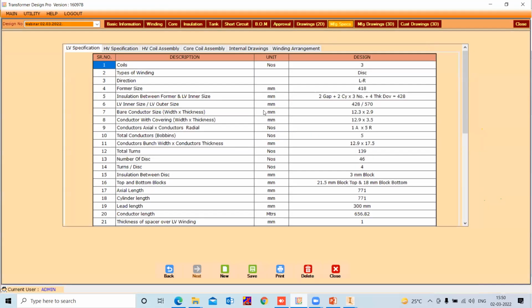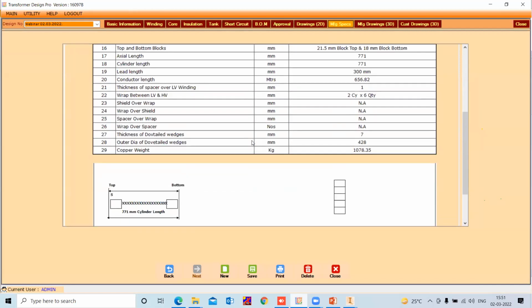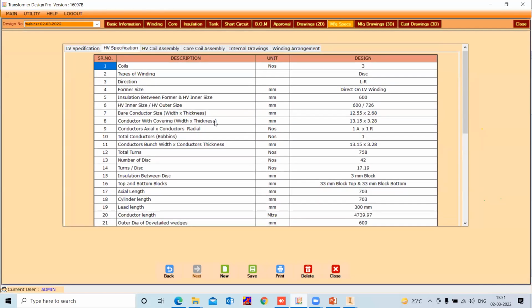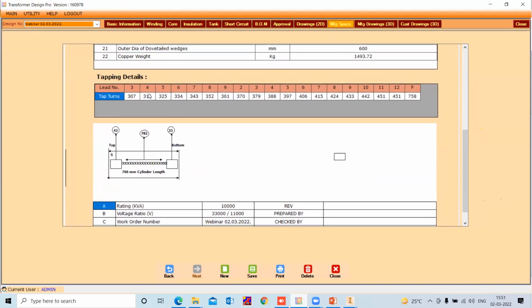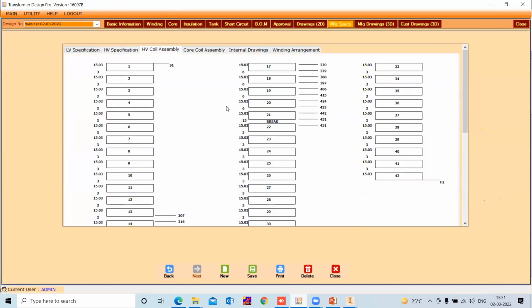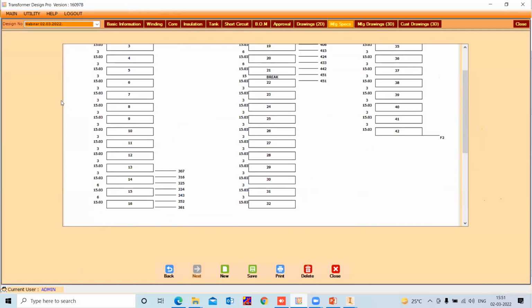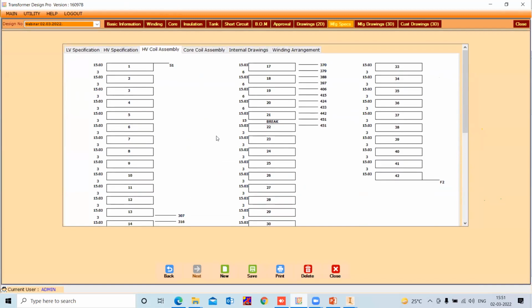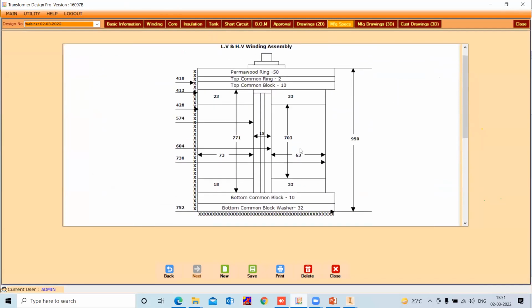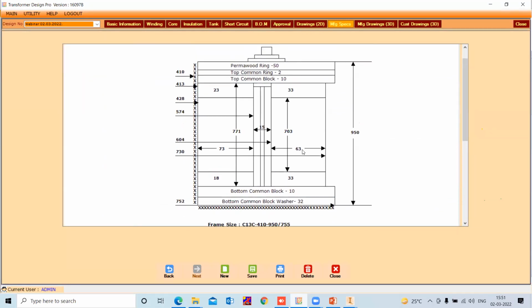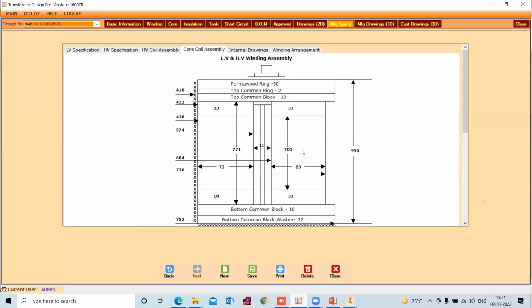Now, let's see the manufacturing specification for shop floor. Then this is the LV winding detail, HV winding detail. You can see the tappings for OLTC, the lead number and tap turns. Then the HV coil assembly. You can see the insulation arrangement in between the discs. There is a 3 mm insulation, but between the tappings, the insulation will change automatically. Now you can see here the insulation diagram, total height and the electrical height, physical height, the gap between core to LV, LV to HV, top and bottom clearances, how we have arranged with the permawood ring, top common ring, top common block. You can also change this value as per your requirement using the insulation page.